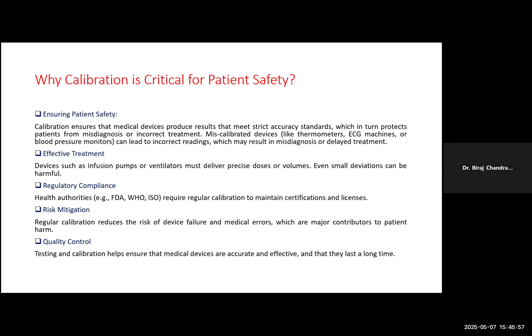Then regulatory compliance. We have to be in compliance with the regulatory authorities, as we discussed in the preliminary slides. Then the risk management process. Risk mitigation: calibration of the equipment will reduce the risk. It will have a risk mitigation effect on the equipment. Quality control: calibrated equipment will always give you quality assurance of the result.